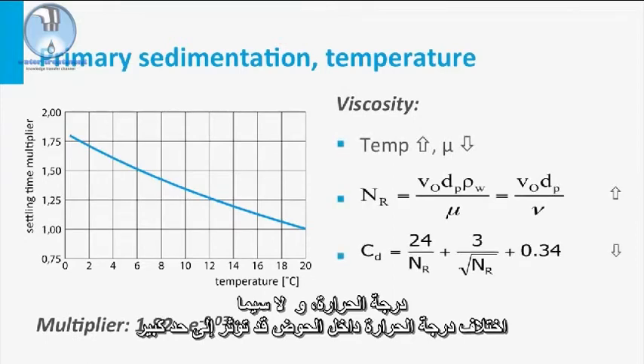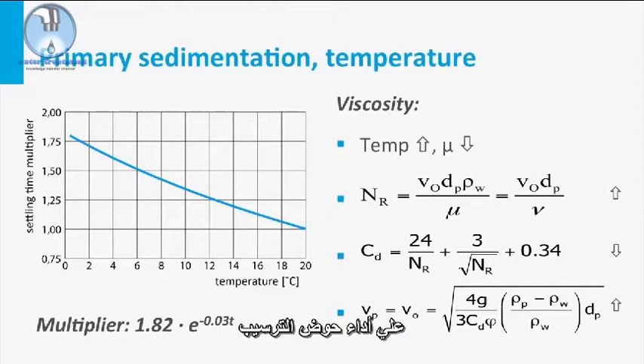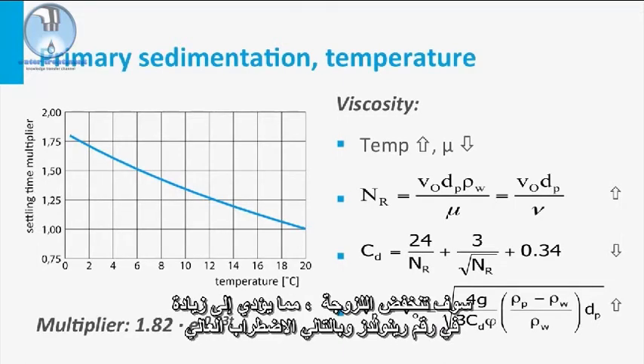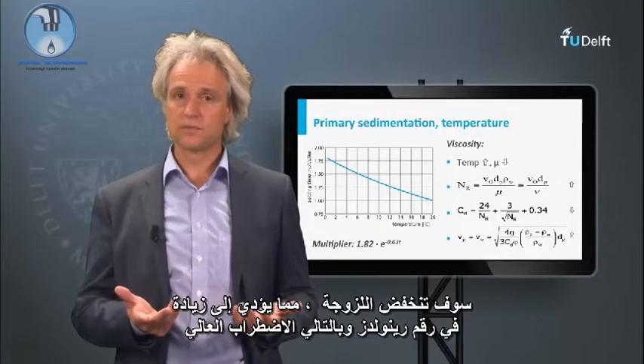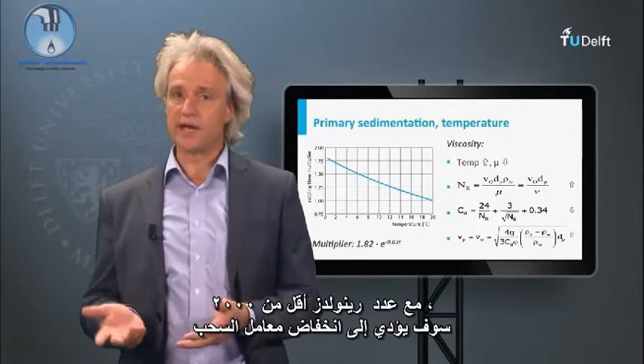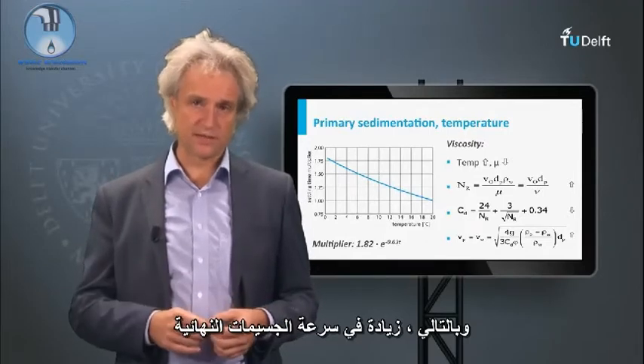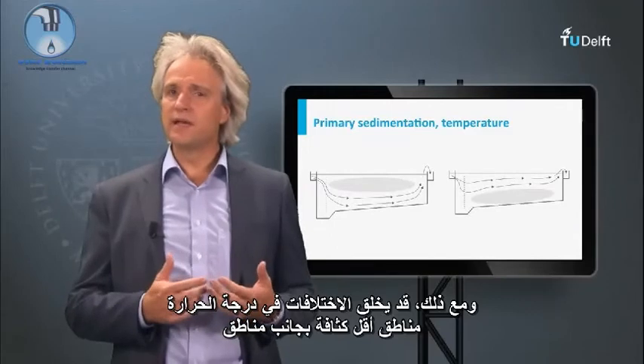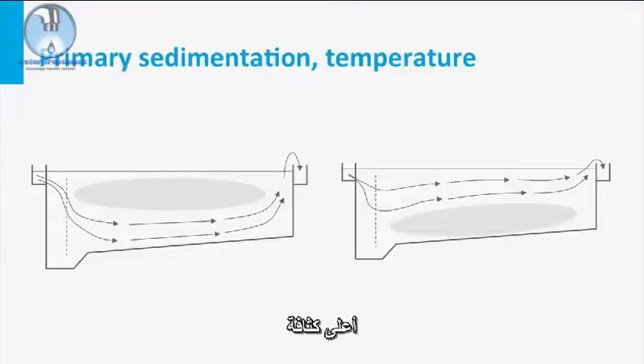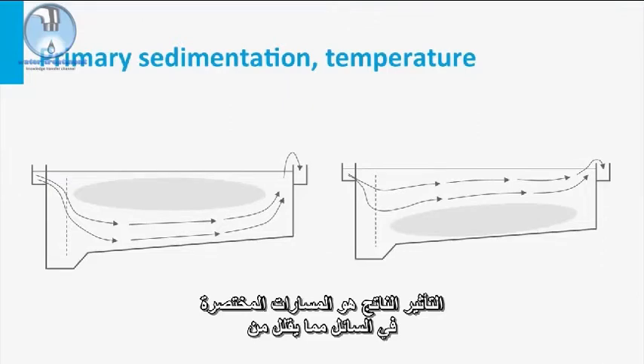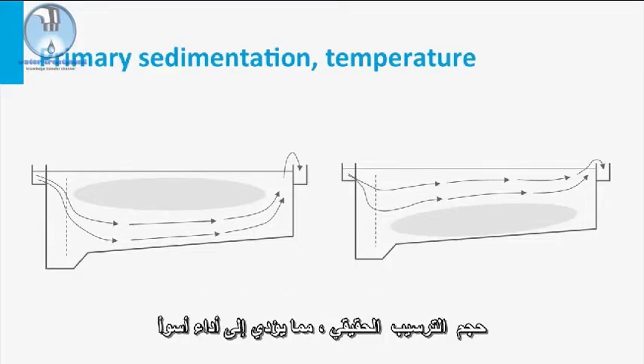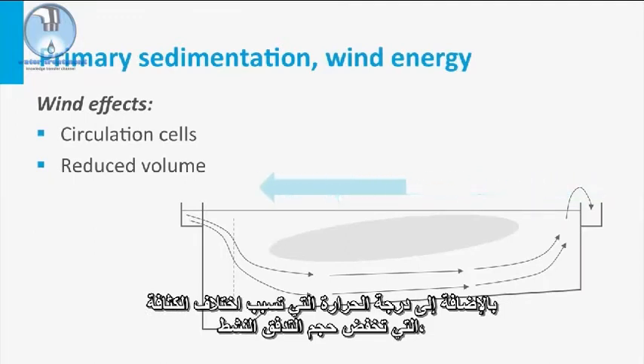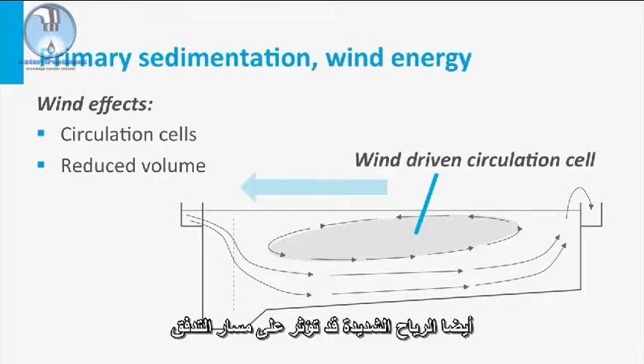Temperature, and particularly temperature differences within the tank, may largely impact the sedimentation performance of the clarifier. From the discrete settling principles, we learned that with increasing temperature the liquid viscosity will drop, leading to an increase in Reynolds number and thus higher turbulence. With Reynolds numbers less than 2000, this will result in a drop of the drag coefficient and thus an increase in the terminal particle velocity, leading to enhanced settling under laminar flow conditions. However, temperature differences may create areas of lower density next to areas with higher density, and the resulting effect is short-circuiting of the liquid, reducing the actual settling volume and leading to worse performance. Density differences may be caused by incoming sunshine, and also strong winds may impact the flow regime.